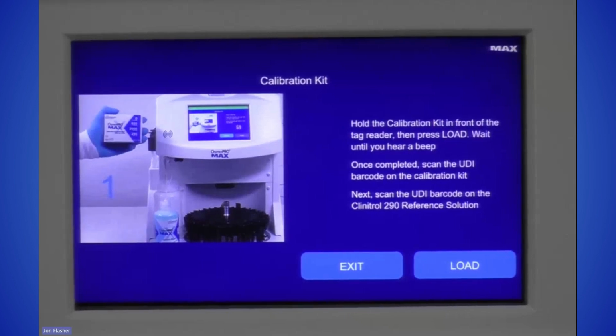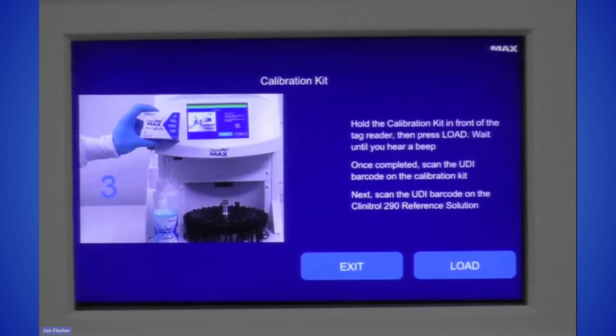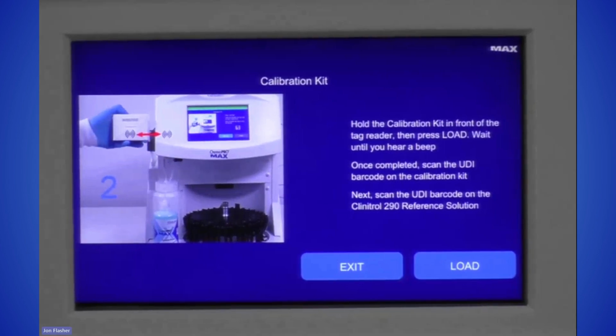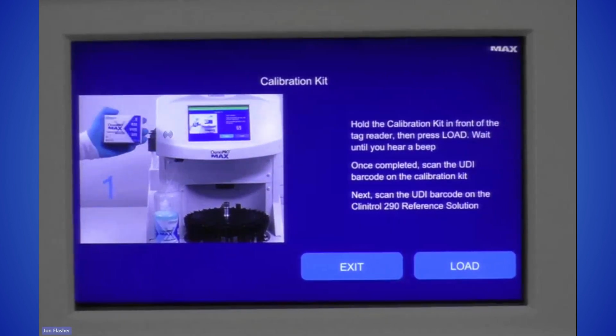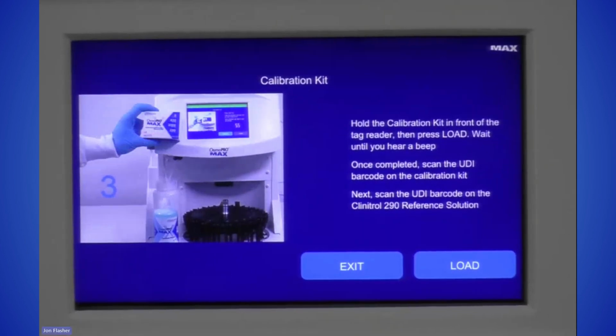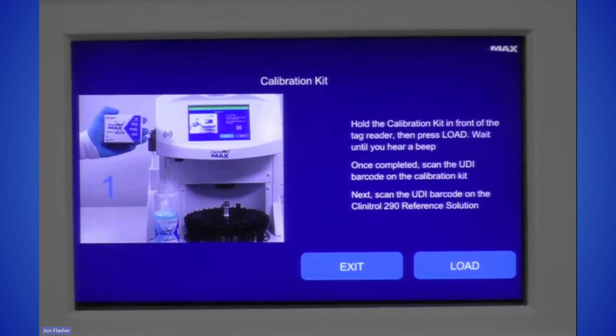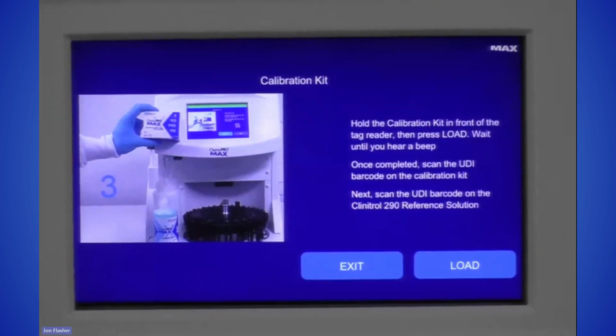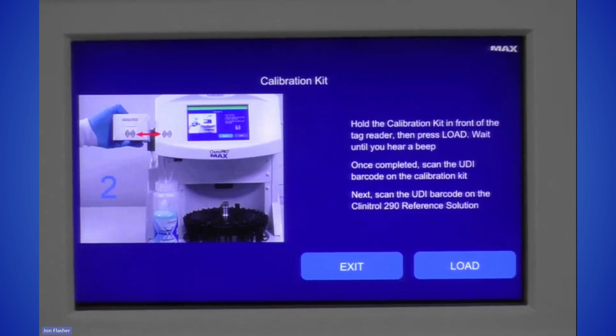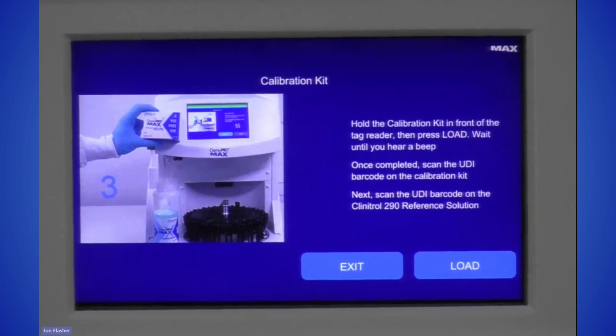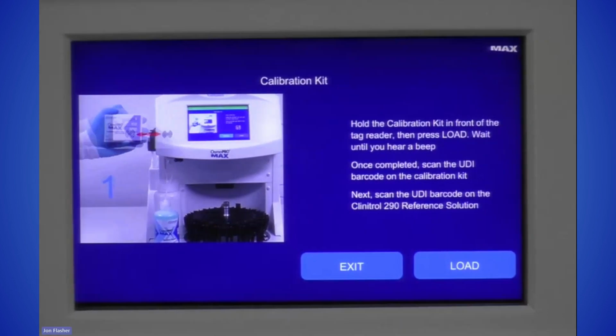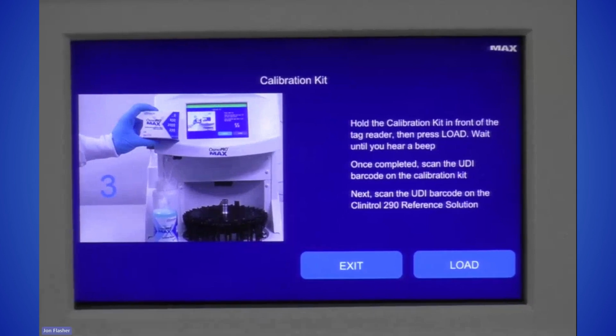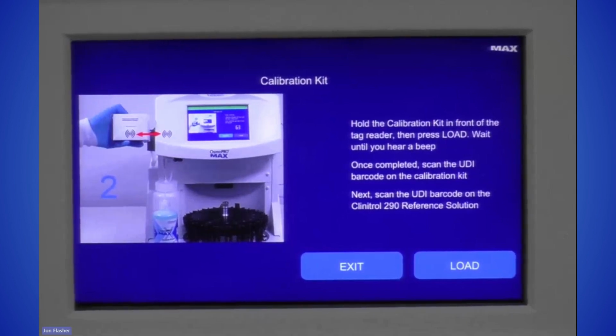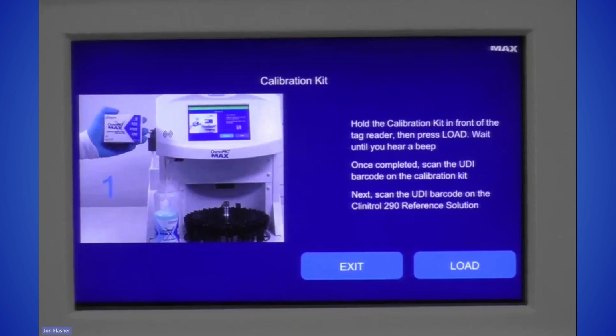So as you can see, the first thing that it's going to prompt you to do is to take your calibration kit that comes with the OsmoPRO MAX and hold the symbol on the back of the box, which is an RFID tag, up to the RFID reader on the instrument. And then if you look on the right hand of the screen here, it'll actually tell you what you need to do next. So after that, you'll go ahead and hit load, and then you'll see another similar video description on how to load all of your ampule adapters into the turntable, what position to load them into, and how to carry out the rest of your calibration all the way to completion. So we're not going to start that because once you start, you got to go through that whole process.